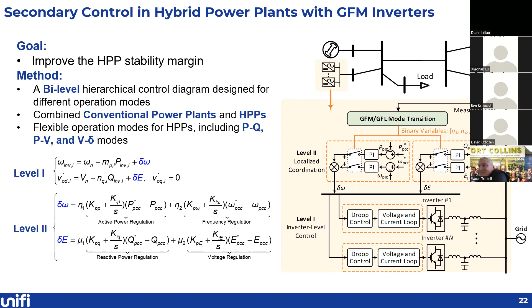For level 1 algorithms, we designed the conventional droop control as the function used here, and in level 2, we designed different modules as detailed. By activating different combinations of the modular control functions in the secondary control level, we can control the HPP as different types of buses, as shown in the overall picture.